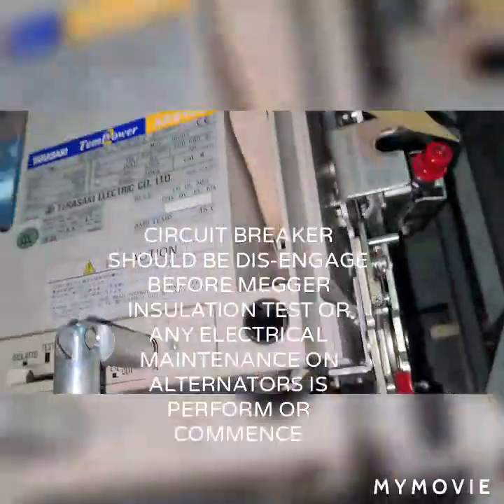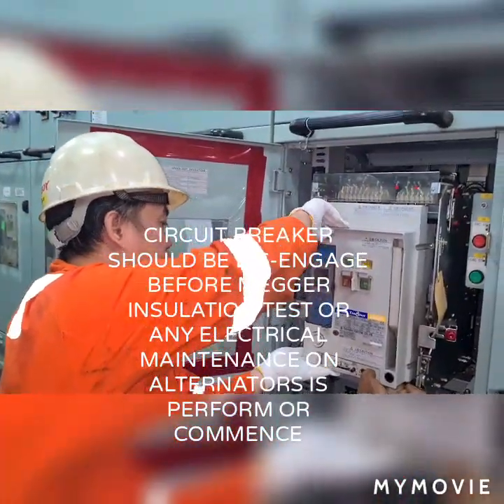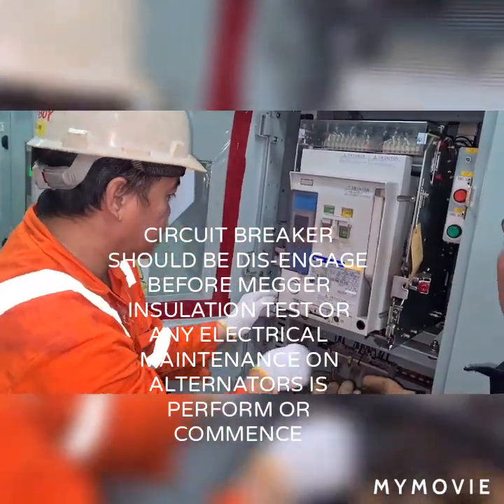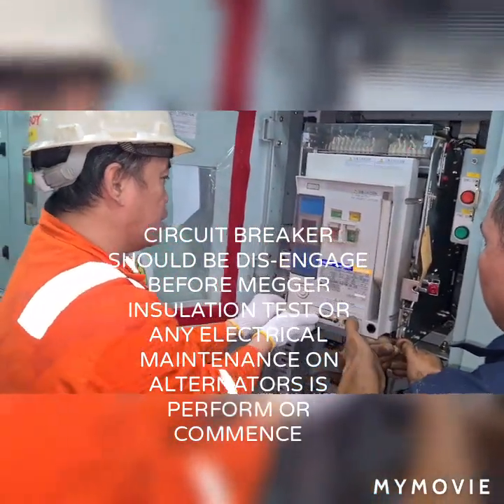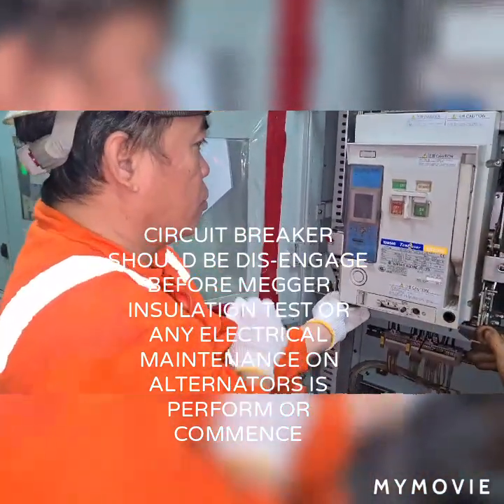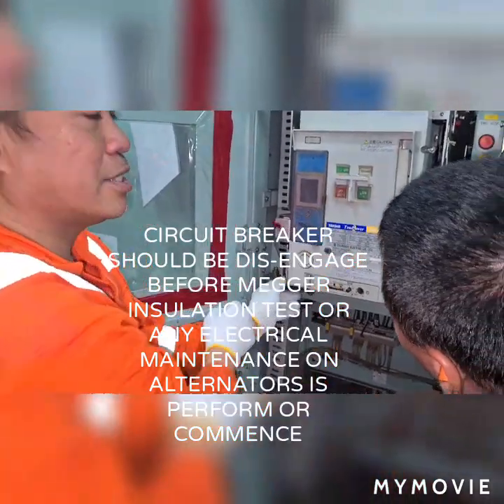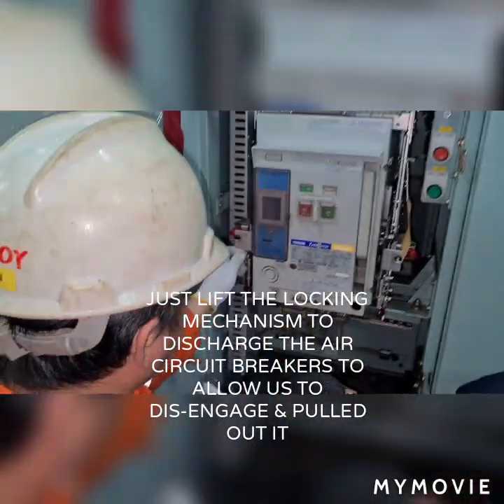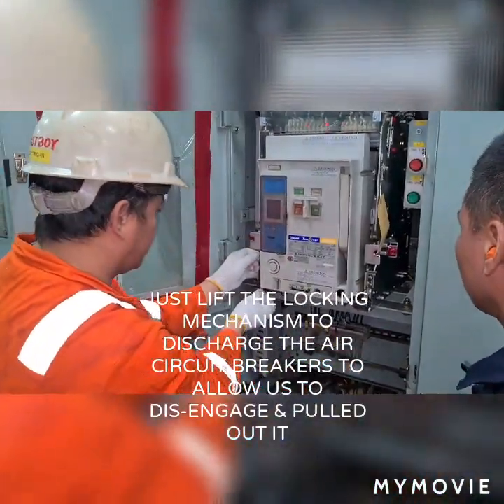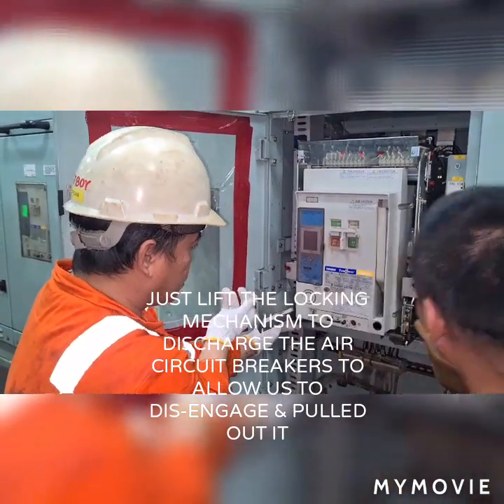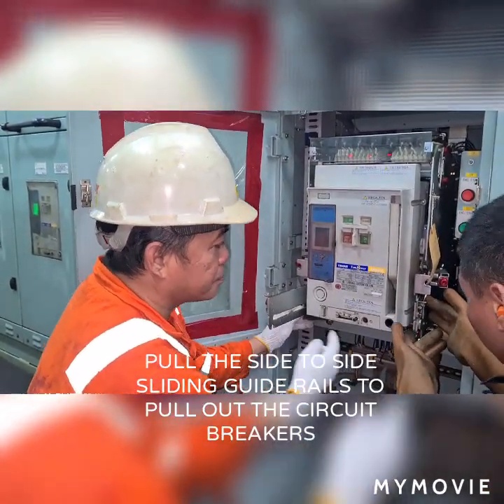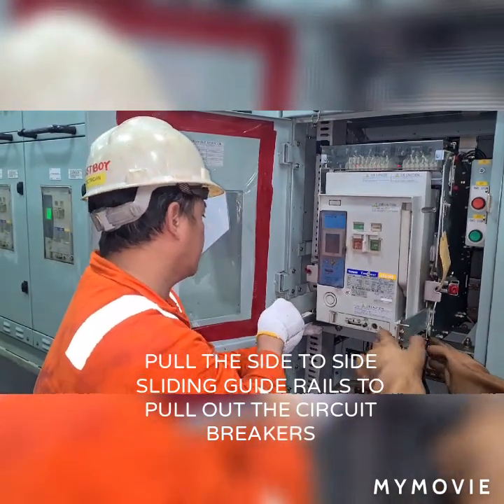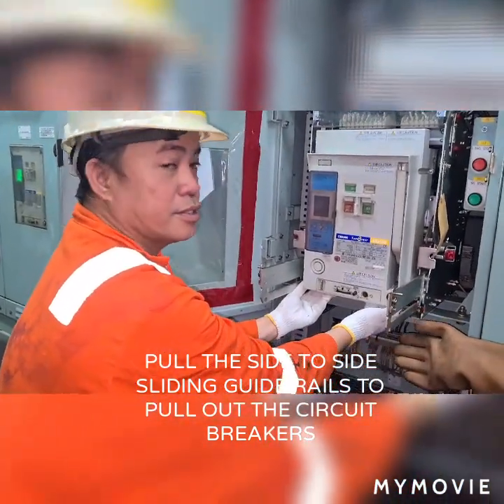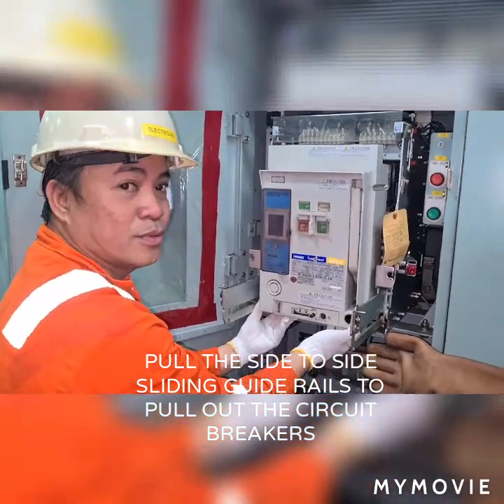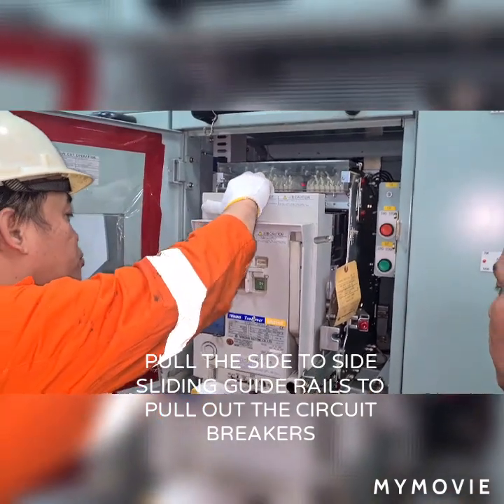Since the circuit breaker is already isolated, we need to do another step to pull it out. By unscrewing the Allen key and making a little bit of a pull, as you will observe, the circuit breaker is being discharged. The yellow charge mark turns into a discharge mark. So once it is discharged, you need to pull the side-to-side guide rails. By pulling them, you can now easily draw out the circuit breaker out of the main switchboard bus bar.